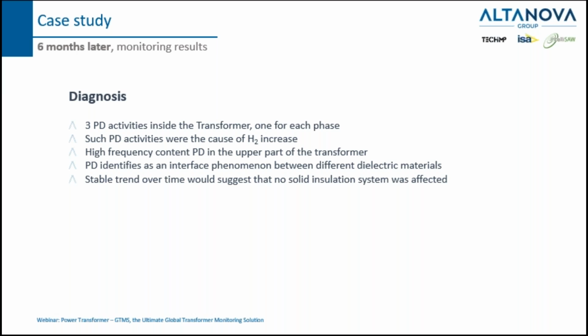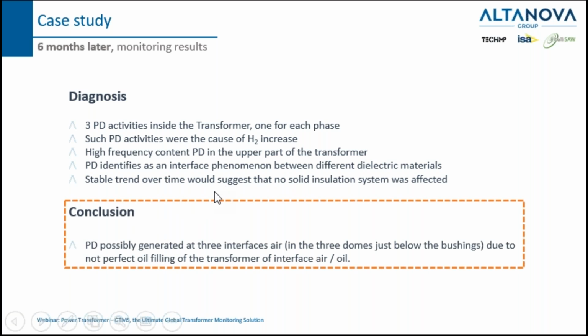We also detected high frequency content PD. That means that it was very close to the upper part of the transformer. It identifies as an interface phenomenon between different dielectric materials with a stable trend over time. The conclusion was that PD was possibly generated at the 3 interface between air and oil in the 3 domes just below the bushings. This is due normally to the not perfect filling of the transformer in the interface air and oil.